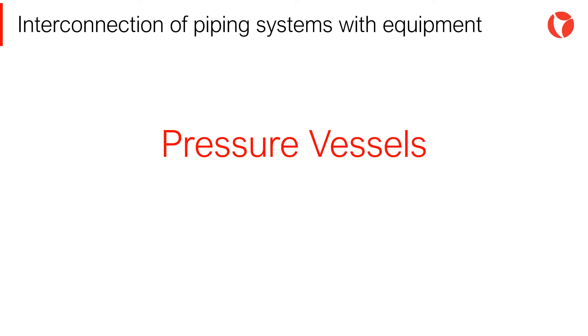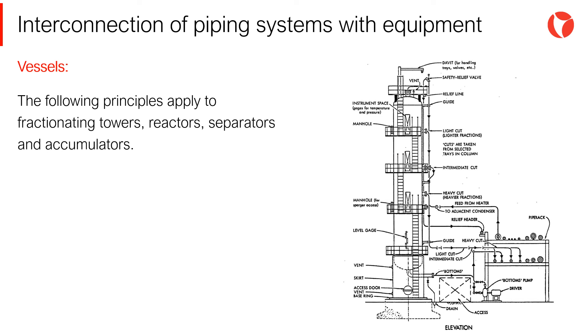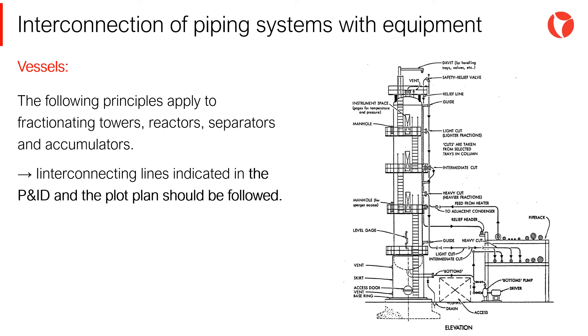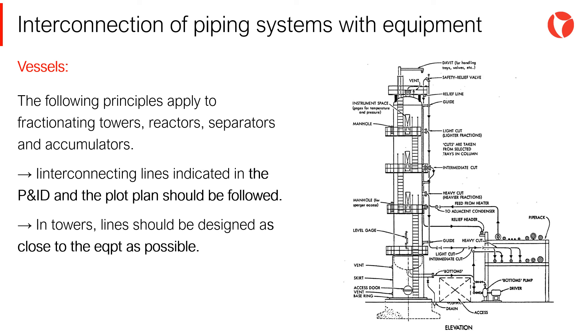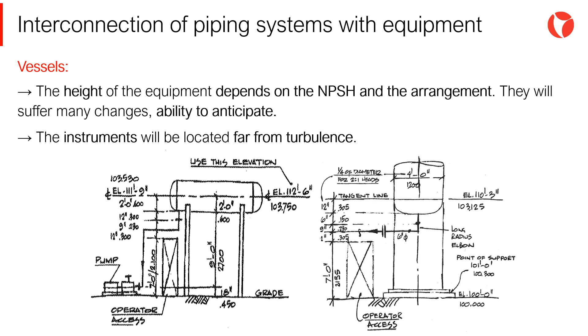The arrangement of piping in pressure vessels is one of the simplest cases, with the exception of fractionating towers. The following principles apply to fractionating towers, reactors, separators, and accumulators. Interconnecting lines indicated in the P&ID and in the plot plan should be followed. In towers, lines should be designed as close to the equipment as possible, and supported on the equipment if possible. The height of the equipment depends on the NPSH of the pump and the piping arrangement. This arrangement will suffer many changes, so the designer should be able to anticipate all these changes.